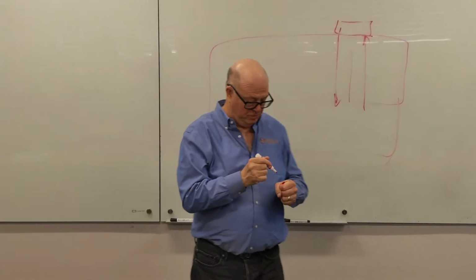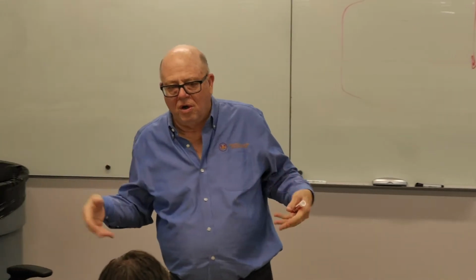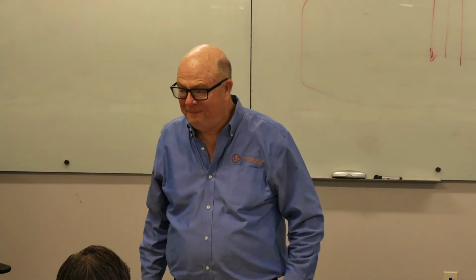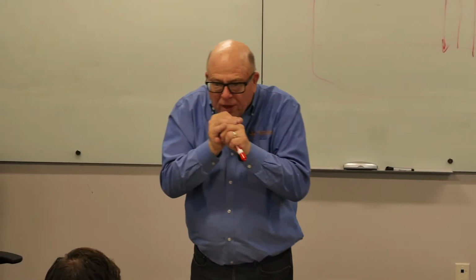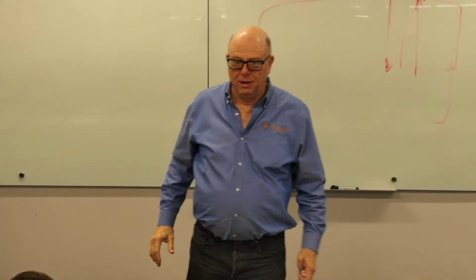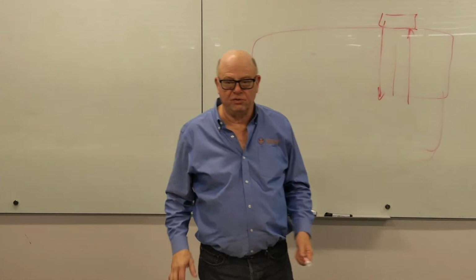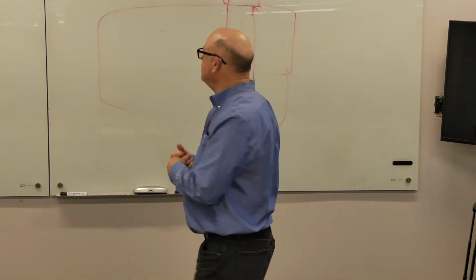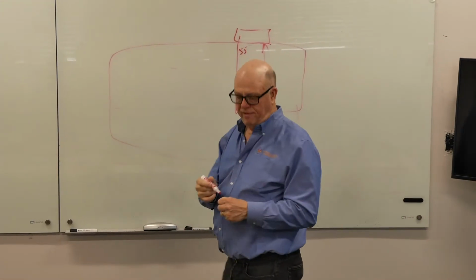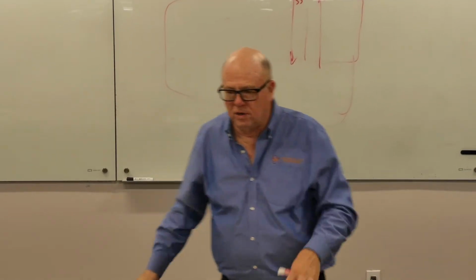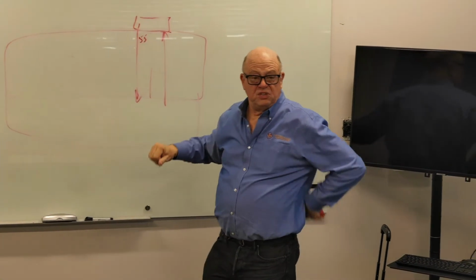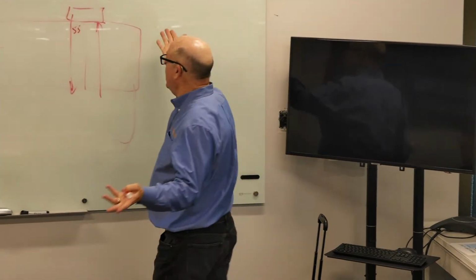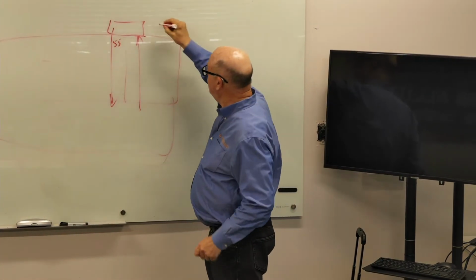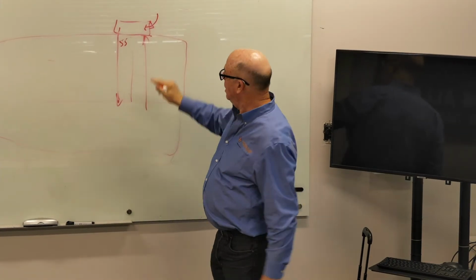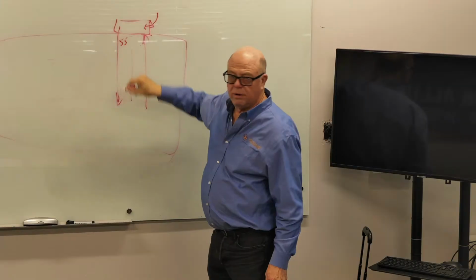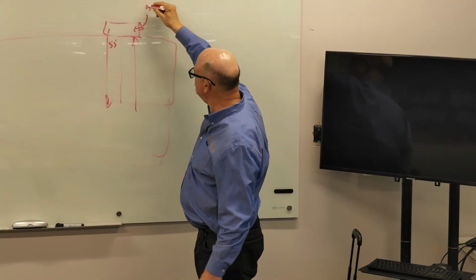So when you go into economizer mode, economizer is called that because it's supposed to improve your energy economy. If you take a paper bag and you blow it up and the bag gets big, that's what you're doing to the building when you go into economizer operation, because when it's cool enough outside, we've talked several times about how ideally the supply air temperature is 55. Well, the simplest way to look at that with an economizer is that 55, 56, 57, whatever temperature air we need, if it's that temperature outside, we shut off the compressor and we pull in outside air through the outside air damper, and we don't take this back around and have to mechanically cool it. We're just using outside air because it's 55, okay?